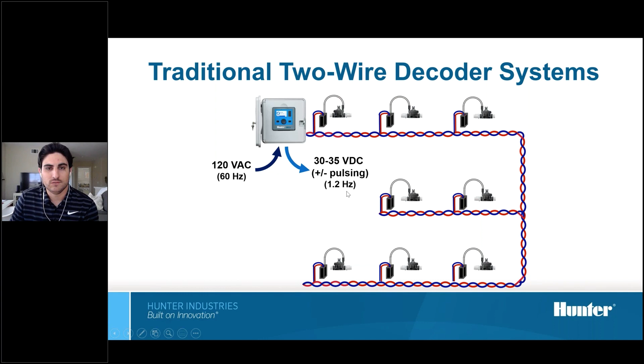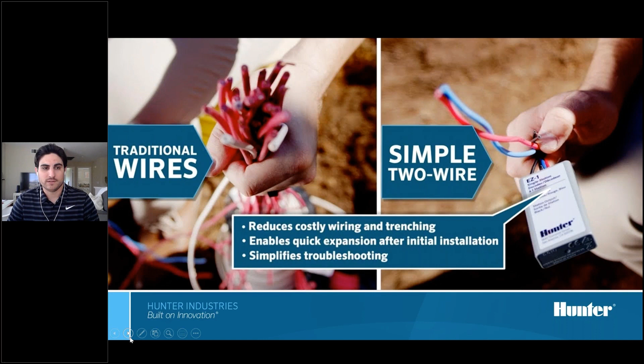Here's a great shot from a video. I think it shows a great comparison: we have a conventionally wired system on the left side, with a big bundle of wires that we have to maintain. You even have to pull some spares through for a project if you're anticipating retrofit or expansion in the future. Lots of wires to maintain, lots of wire connections to maintain, and it can get a little busy. With a two-wire system, all you have to do is route that twisted pair through, have a simple trench, and then you can just splice onto the end of that two-wire path to continue your system expansion. So, a lot less wire, a lot less labor and materials. Big benefits there, only running a two-wire through the entire system.